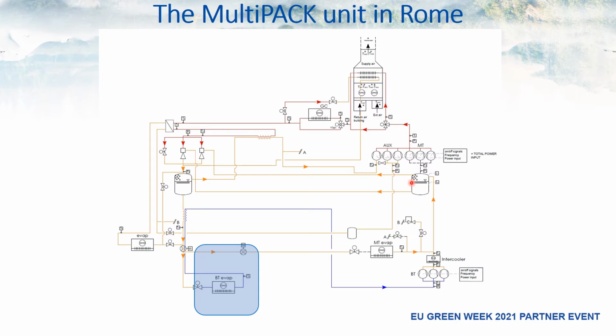The unit is serving low temperature and medium temperature evaporators, and it's also serving the air handling unit. In the winter time, we have direct flow of CO2 from the discharge line of the compressors inside the air handling unit, and in the summertime, we can expand CO2 after a gas cooler inside the cooling coil of the air handling unit. We have an additional outdoor evaporator, which can work as an additional heat source to feed the heat pump functionality in the winter time.